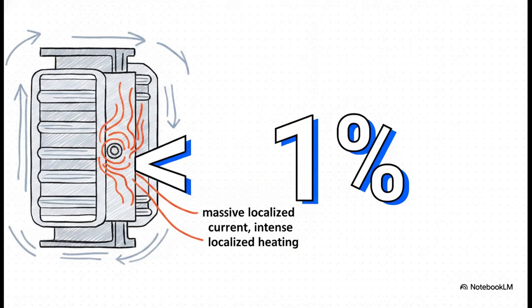Think about this. A single shorted turn in a winding with hundreds of turns might represent, literally, less than 1% of the total winding. Less than 1%. Yet that single short creates this tiny, low-impedance loop. And because of the magnetic flux in the core, that tiny loop circulates absolutely massive, localized currents. We're talking currents many times higher than the transformer's normal rated current. But because it's completely confined to that tiny loop, it generates intense, severe heat that is totally invisible to your standard overcurrent measurements. The big picture looks perfectly fine, but locally it's a disaster.